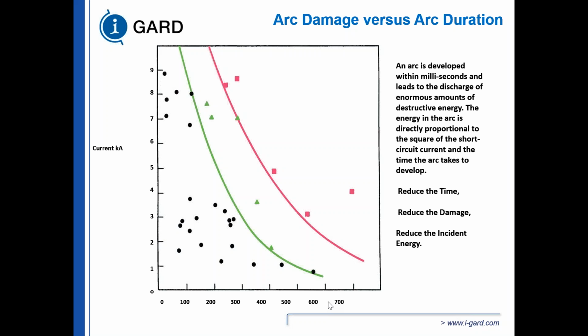One of the professors at Johns Hopkins University did a lot of testing on solidly grounded systems and arc flash protection, arc flash incident energy. What they found is any arc that was low in nature and the duration was very, very low, if it fell below this green line, then you had superficial smoke damage. Any faults with arcing fault current and duration that were between the green line and the red line had surface damage, and any faults above the red line in fault current and duration burned through the steel. So you can see it doesn't take much.